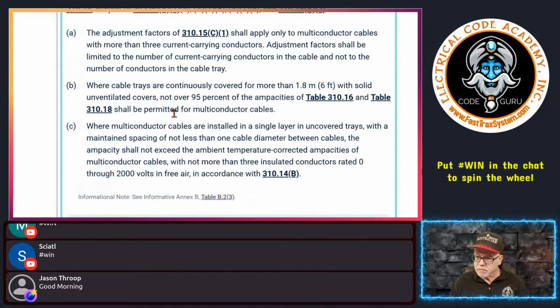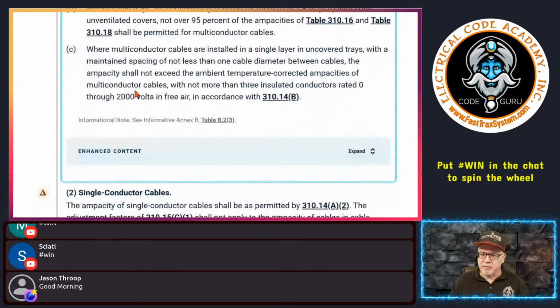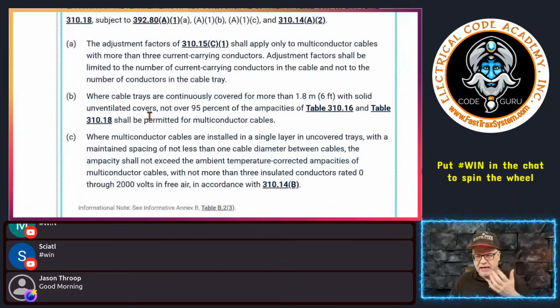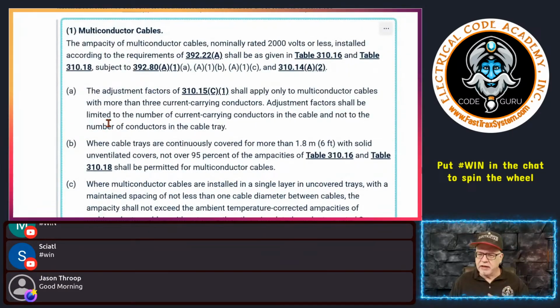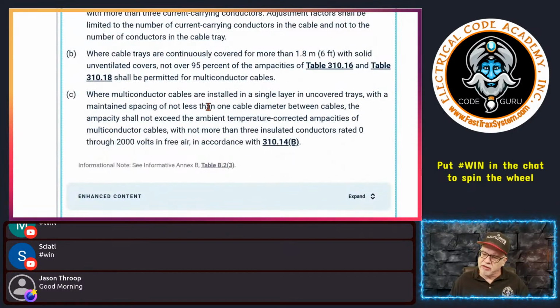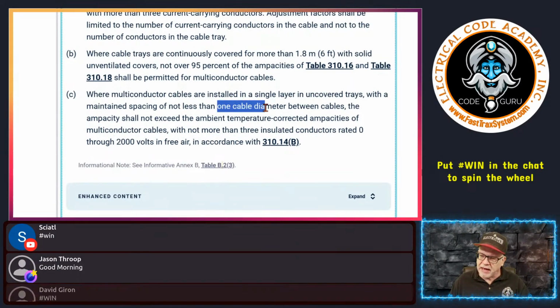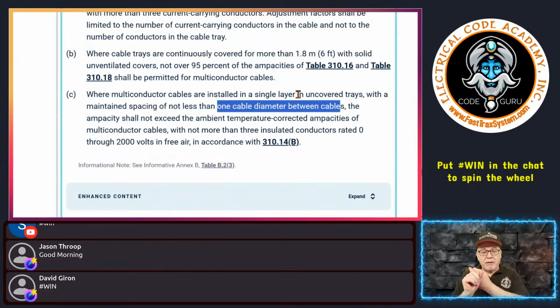Okay. Next one here, when it comes to ampacities, again, we are talking multi-conductor cables. It says where the multi-conductor cables are installed in a single layer, okay, in an uncovered tray with a maintained spacing of not less than 1 cable diameter between the cables. And y'all saw me talk about that the other day, and I said I would allude to it as far as ampacity today. But that is a situation, and we do have a picture of that, in case everybody's like, okay, what are you talking about?